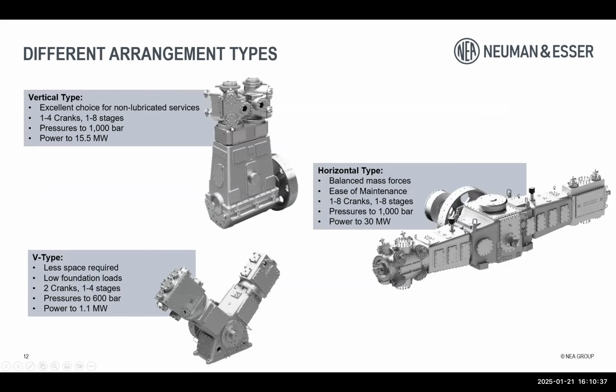In terms of reciprocating compressors, the piston type, we have three different designs. The vertical compressor is an excellent choice for non-lubricated services. You can reach up to 1,000 bar on them. For non-lubricated hydrogen compressors, we can now deliver up to 500 bar on a reciprocating compressor, getting the gas out of a PEM electrolyzer at 30 bar. So this is very important for heavy-duty refueling stations that need a lot of gas at 500 bar for 350 bar filling. This vertical reciprocating compressor is an excellent choice.